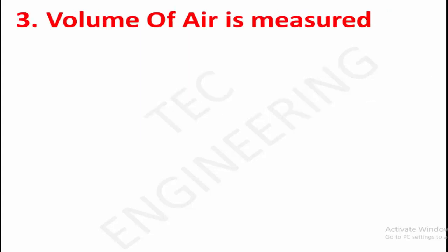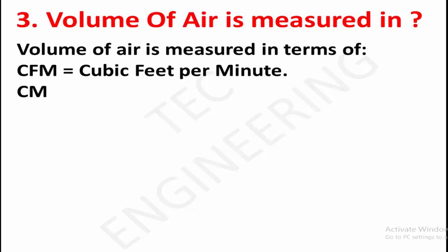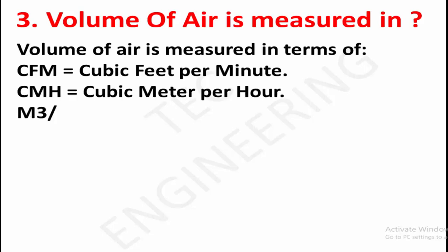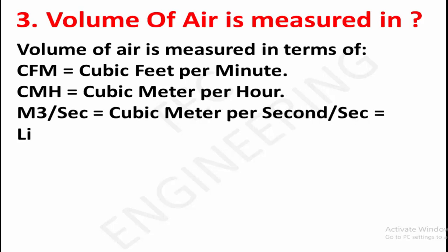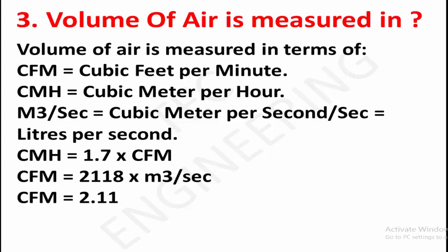Volume of air is measured in terms of: CFM — cubic feet per minute; CMH — cubic meters per hour; M3/sec — cubic meters per second; L/sec — liters per second. Conversions: CMH equals 1.7 × CFM; CFM equals 2,118 × M3/sec; CFM equals 2.119 × L/sec.